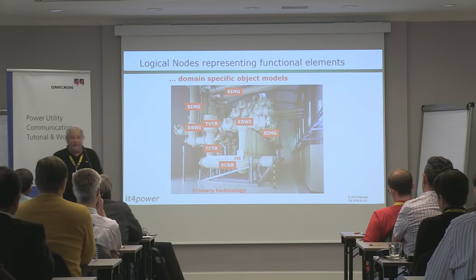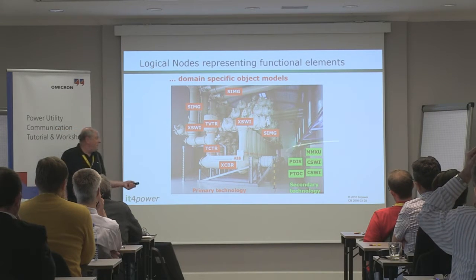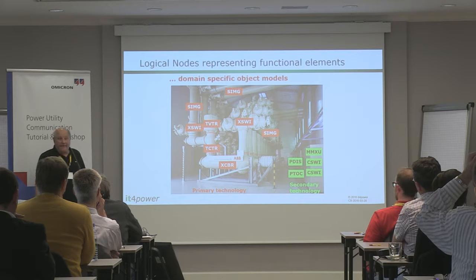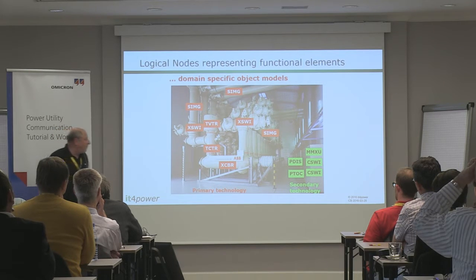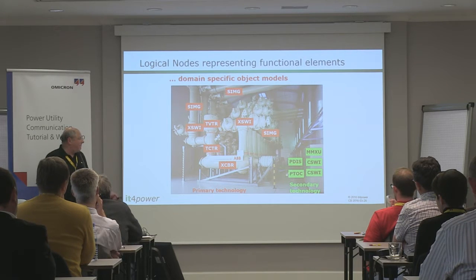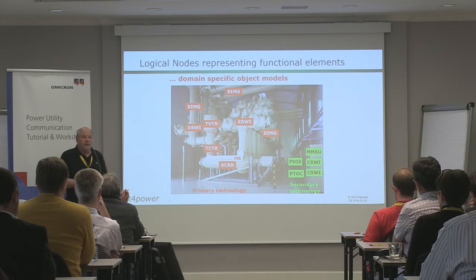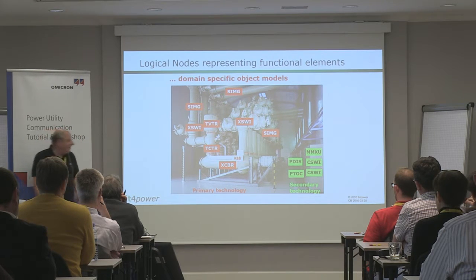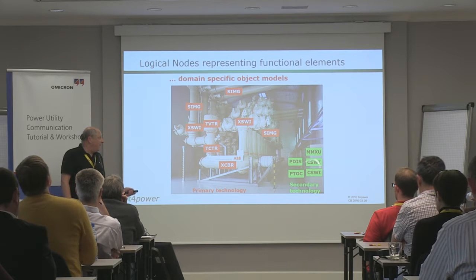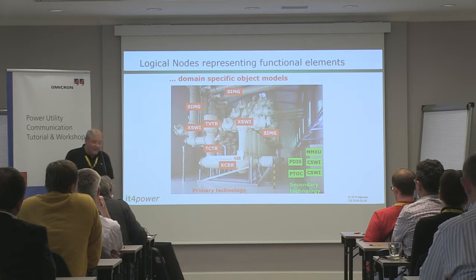Substations also have software applications like protection, and 61850 defines logical nodes to model the information from these functions as well. Examples include a measurement logical node providing rated values for current, voltage, and active power; frequency measurements; distance protection elements; time overcurrent elements with start and operate information; and potentially associated settings. There are also logical nodes for control functions, such as controlling a circuit breaker or disconnecting switch.